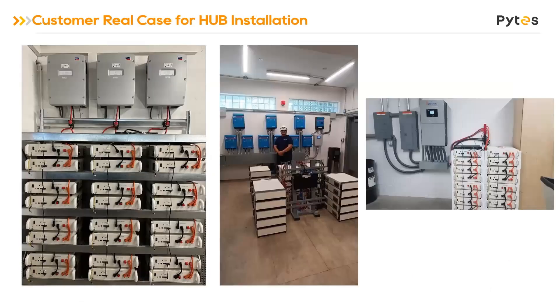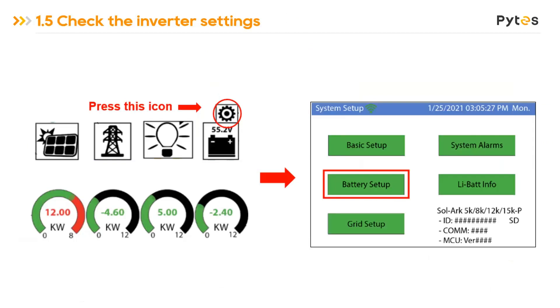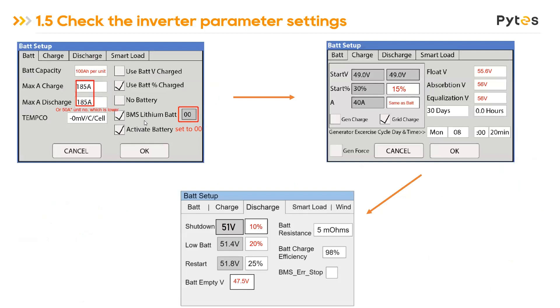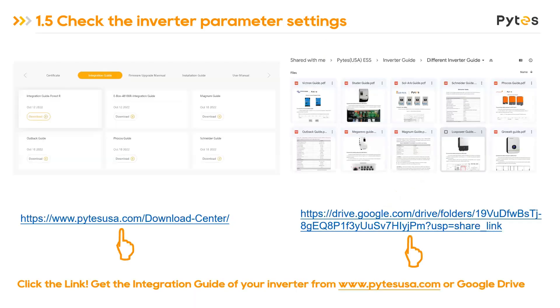Here are some real installation examples of hub setups from our customers. Next, check the inverter settings. Taking Sol-Ark as an example: click on the settings icon and go to battery setup. The BMS Lithium Batt option is there — set it to 00 for CAN communication protocol. This is the key setting for communication. The remaining settings are operating parameters mentioned in detail in our integration manual. You can get all inverter integration manuals from our website and Google Drive, or email us for help.